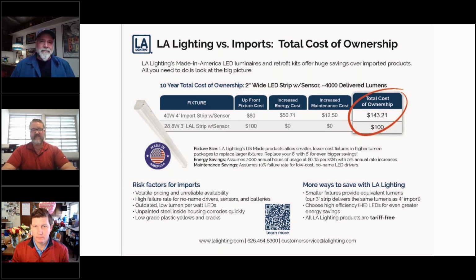We ran tests on the sensor in that fixture, and it wasn't picking up occupants as well as the customer wanted, so they had to put longer delay times on it to make up for the fact that it would turn off when you weren't standing right underneath it. When you run the costs on energy consumption, between going from 40 watt to 28 watt with the same lumen output, and getting tighter on our occupancy sensors with EnOcean, we're saving $50 extra on that fixture over 10 years.